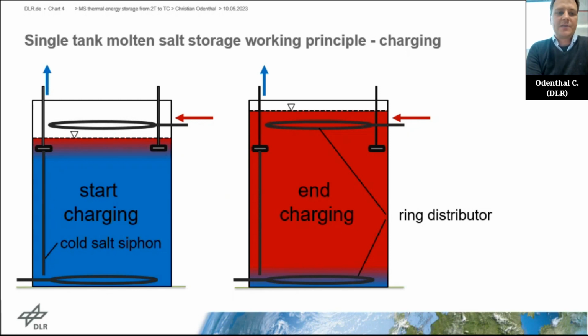And here you see basically the working principle of the system. Okay, so you can extract the cold salt from the bottom with a pump and simultaneously add hot salt at the top through a distributor ring. And then over the course of the time, as you extract the cold salt and add hot molten salt, you end up with this situation that you have the tank completely filled with salt. And what you can also observe in that case is because of the lower density of the hot salt, you will have a higher filling level on the tank after the end of the charging process.